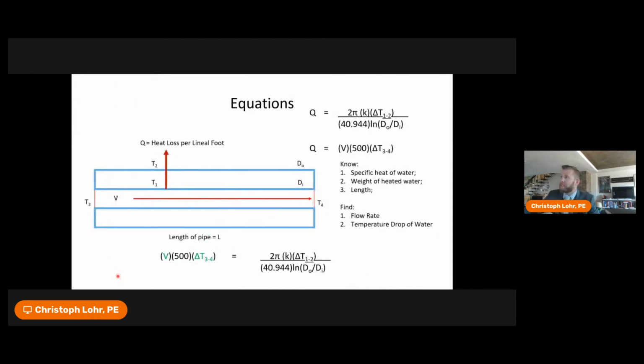All right, the second equation is our flow rate and temperature drop through a given length of pipe. So again, we have our conductive heat losses. That's our T1, T2, which we've determined based on the charts before. But those two heat losses should be about the same. And so when we have that fluid flow going from T3 to T4, we have a certain flow rate and a temperature drop there. So we know, based on the water heater, let's say it's set for 140, what our T3 is. To figure out what T4 is, we have to make a calculation, not an assumption, but a calculation based on an assumed flow rate. And typically flow rate is the starting assumption point.